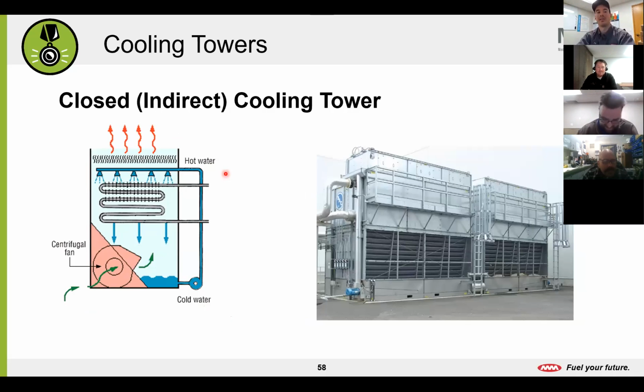So here is the closed style cooling tower. What that means is that our condenser water loop is never in direct contact with the outside air, so all the dirty contaminants stay out. In this picture, our condenser water loop is coming in from, let's say, the building again, the hydronic building that's running all cooling and the water loop's getting hot.